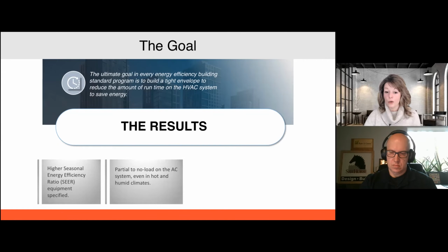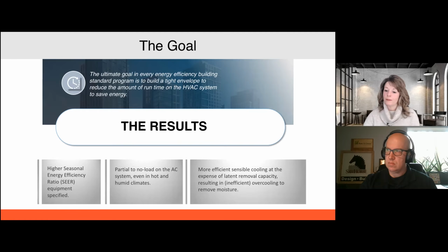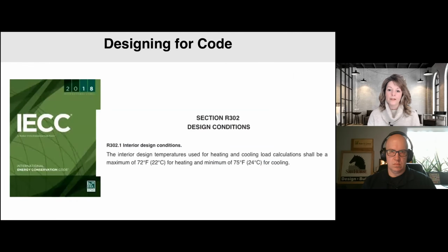We're seeing a lot of no load to partial load run times, even in hot, humid climates. When we get that envelope right, we are drastically changing the amount of runtime on those systems. And then the more efficient sensible cooling comes at the expense of latent capacity, resulting in overcooling to remove moisture. So the system should be set up to overcool a little bit, but we don't want to create comfort issues, and we don't want to create the potential for hitting dew point and developing condensation as well. So we've got to be careful on that overcooling. So designing, in the IECC 2018 code, the minimum that you can design for cooling is 75 degrees.